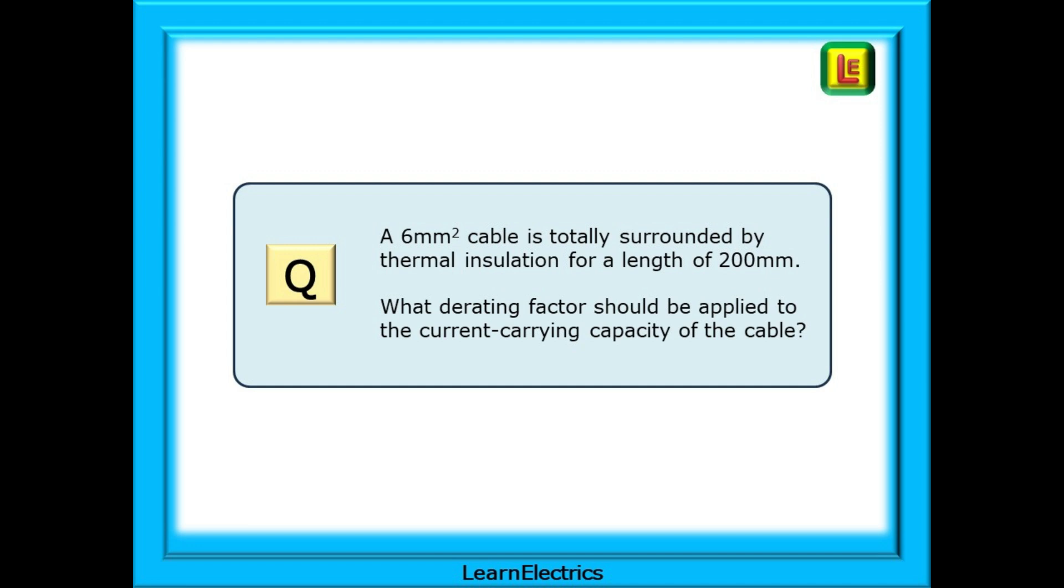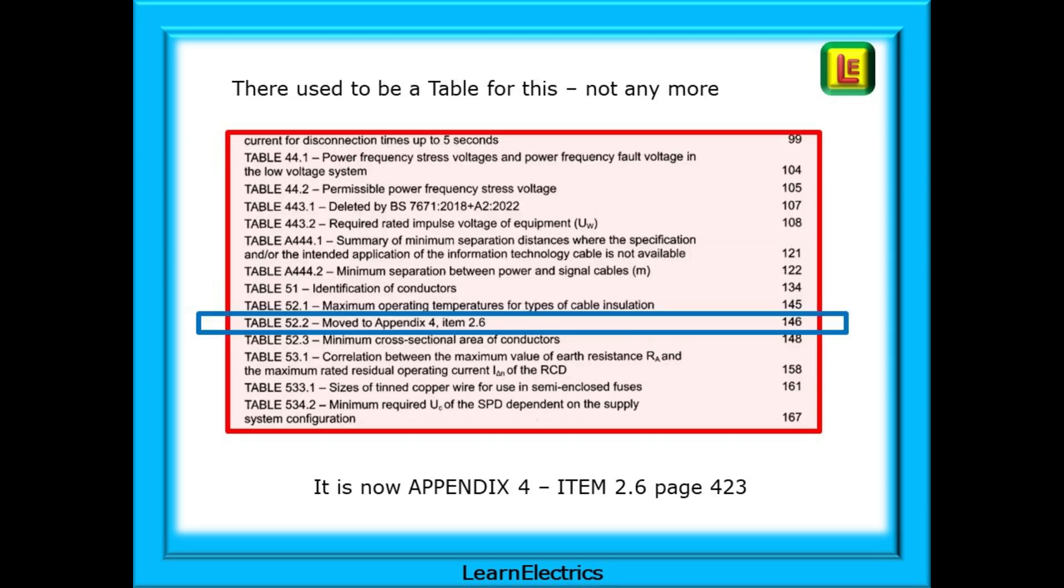A frequent exam question and something that often comes up on site is this: A 6 square millimetre cable is totally surrounded by thermal insulation for a length of 200 millimetres. What derating factor should be applied to the current carrying capacity of the cable? There used to be a table for this but not anymore. Table 52.2 has an entry near the middle of page 573. The book tells us that this has now been moved to appendix 4 as item 2.6 and it is no longer found on page 146. But we will find the table in appendix 4 on page 423. Let's go there now.